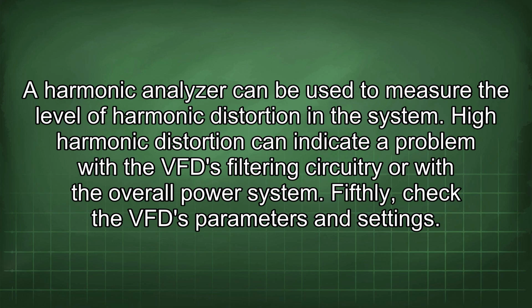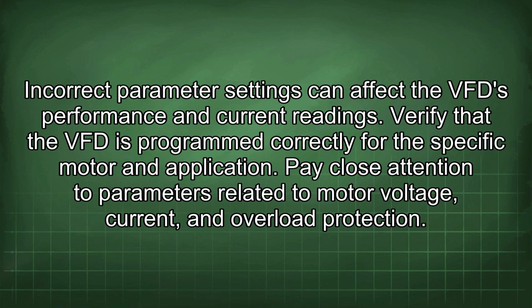Fifthly, check the VFD parameters and settings. Incorrect parameter settings can affect the VFD performance and current readings. Verify that the VFD is programmed correctly for the specific motor and application. Pay close attention to parameters related to motor voltage, current, and overload protection.